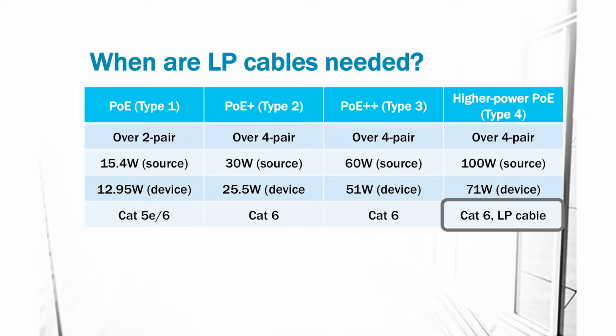Some manufacturers aren't rebranding their cables. They say that their cables already meet that requirement. They don't want to spend the time to update their manufacturing or their marketing or their PDFs, cut sheets. Whatever the reason, they're not adding the special LP designation. And there's an exemption in the NEC. At the end it says, okay, you don't need to run an LP cable, but then you need a professional engineer to sign off and do the design to say that what's being installed is appropriate and will work appropriately. So again, 60 watts and under, Cat 6 is fine. If you've got some forward-thinking clients, or you know you want to design around that 100 watt, then that's when that LP cable comes in.